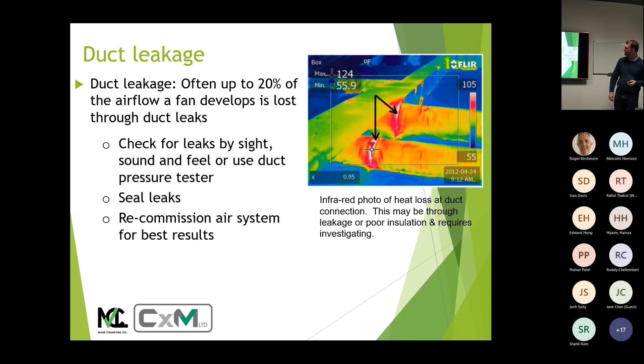Calcs there. There we go, some calcs. So if you're running a fan at 40 hertz, roughly 2.1 kilowatts, they have to run it at 48 because you're chucking out lots of extra air into places you don't know where it's going. You're now going up to 3.5 kilowatts, a 69% increase in energy to provide the same amount of air. Times that by 24/7 in some systems, and that's a huge amount per year, right? And that's only on a 12 by 5. You're saving quite a bit per system. That's not a big system. A 3 kilowatt motor is fairly small. There'll be lots of those in the building.